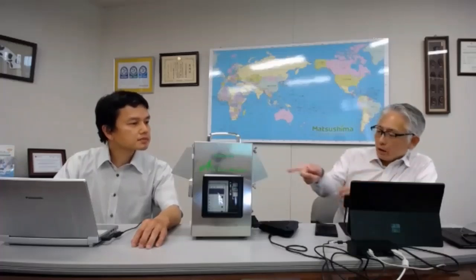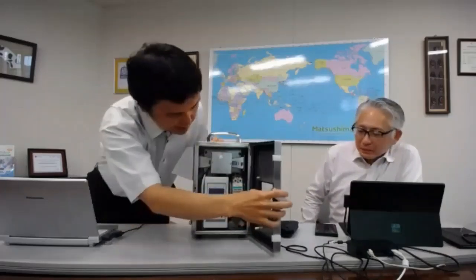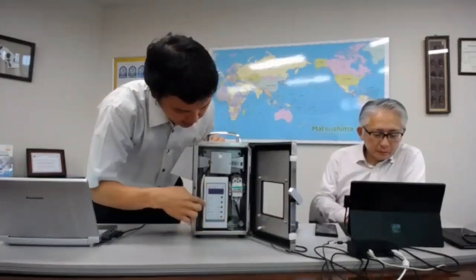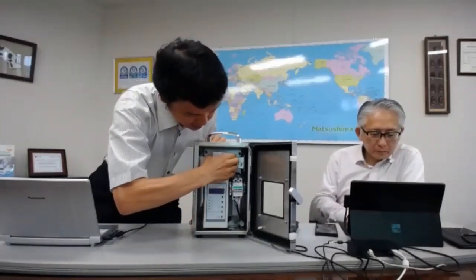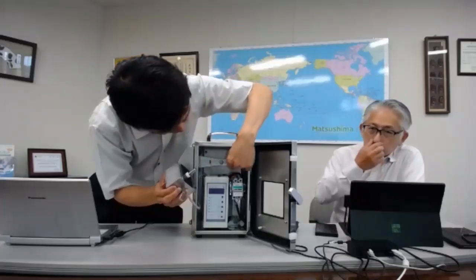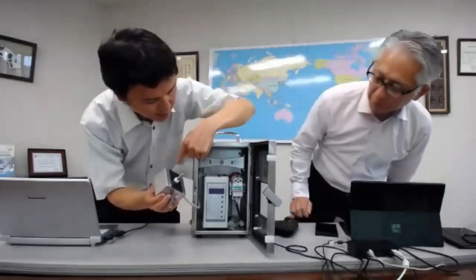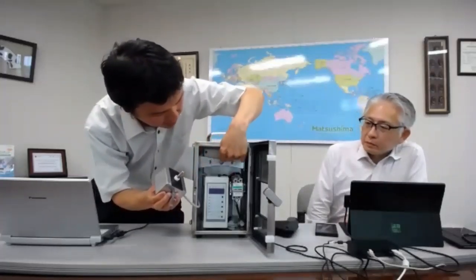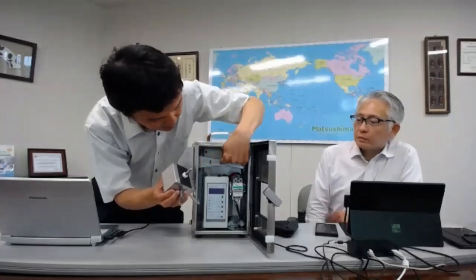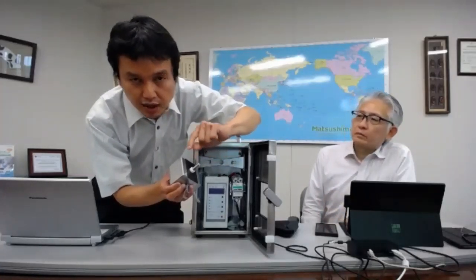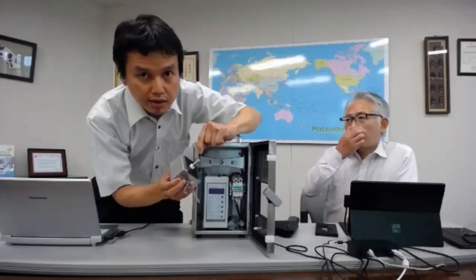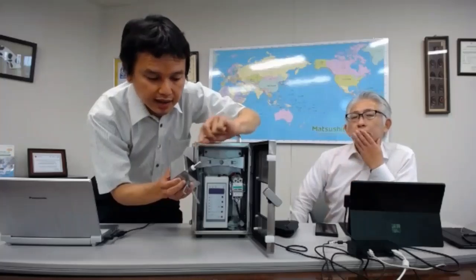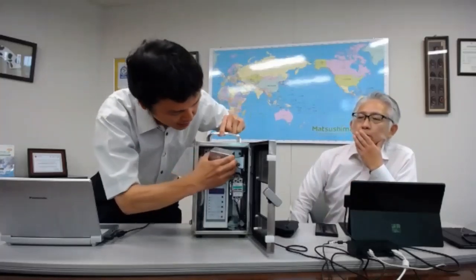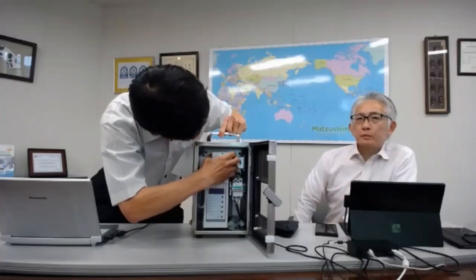So the cleanup, are you talking about the probe? Yes. This is the actual demo unit, and we will open it. This is the power supply and controller, and here is the sensor part. You can take out the sensor and see the short piping. This is the intake part and this is the exhaust part. Air is taken in here, goes through the short pipe, and goes out. This is the sensor part, which is very sensitive, so you have to clean it if material covers it overall. After a dry run, you can clean it up easily for maintenance and then put it back. So it's very easy.